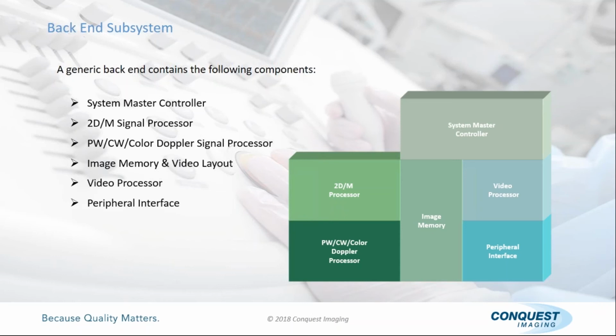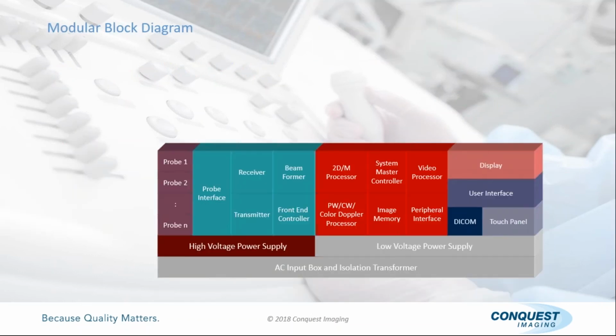Then we add the system master controller. Anybody have any idea what the master controller really is made up of? Anybody have any idea? What changes a Windows computer into an ultrasound? Your application software. Okay? So what we do is we have this Windows computer, and then we add application software, or they call it a shell, because it locks you out of Windows at that point. And when you're locked out of Windows, you can't do a lot of the things they don't want you to do: change resolutions, surf the net, all that stuff that they don't want their operator to do. And it becomes an ultrasound system. So that's what the master controller is, that and the input from the operator. It tells it what probe it wants to use and so on. Okay?